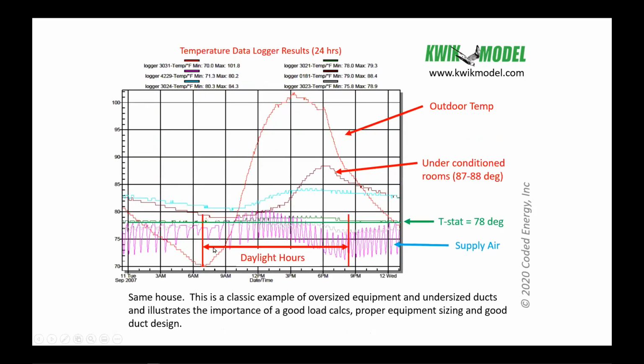Oh, here's another interesting thing. Let me go back to this slide. Notice this short cycling during the day, and here's the outdoor temperature. So, you know, the sun comes up about 7 in the morning and you really see the outdoor temperature go from 70 degrees and shoot all the way up to over 100 degrees within about 7 hours. At 3 o'clock it peaks out, okay? And then it drops back down, the sun goes down and the outdoor temperature gets well below the thermostat setting of 78 degrees, okay? It's 70 degrees outside at night, or gets down to 70 degrees.